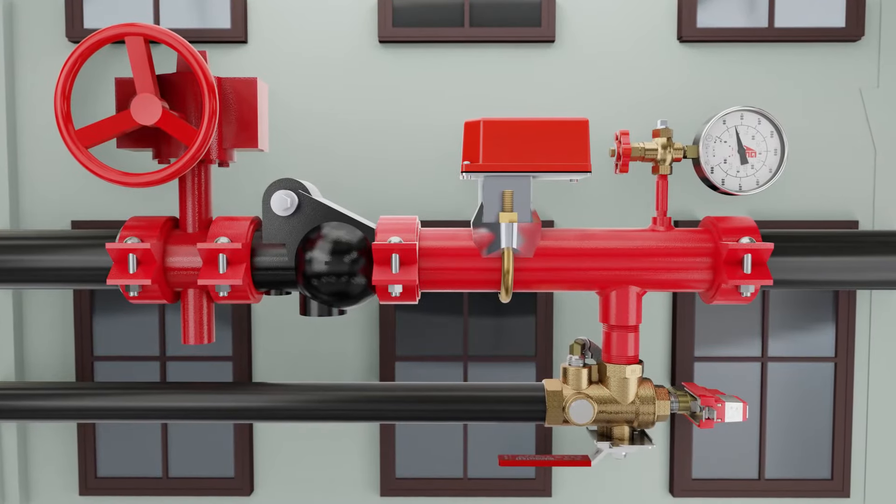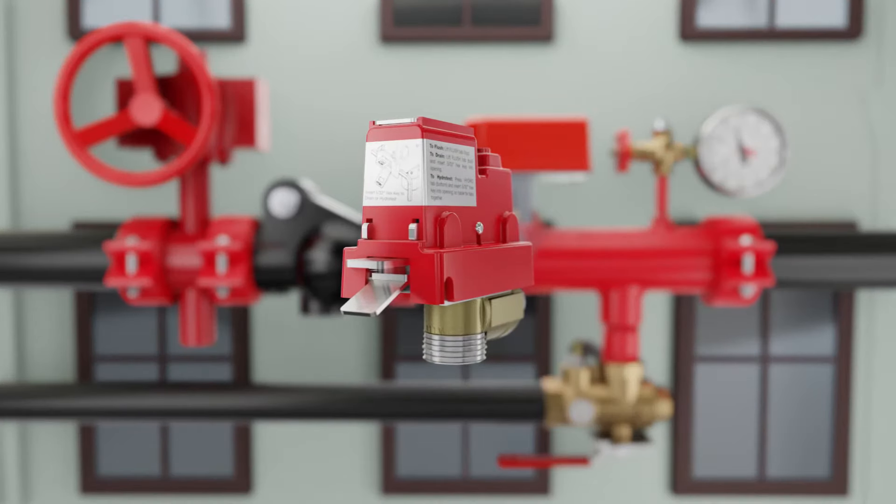AGF's 1/2-inch Model 7000L and 3/4-inch Model 7200L are UL-listed and FM-approved pressure relief valves that can be installed prior to hydrostatic testing and temporarily locked closed to perform system integrity testing.